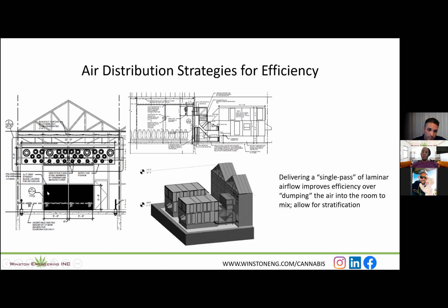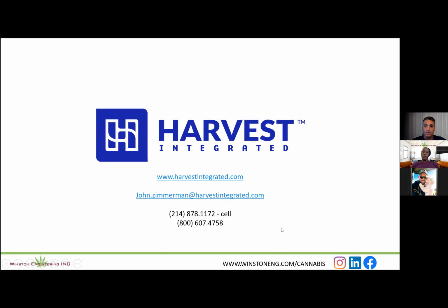Also, what you're looking at here on the bottom is our return air. So the idea is that we've got one fresh single pass loop of air going to the space and back from the space. That will help you save energy if you're able to do that. The alternative is you've got to dump that air into the space at cool enough and dry enough conditions that it mixes with all the heat in the space to give you what you're looking for.